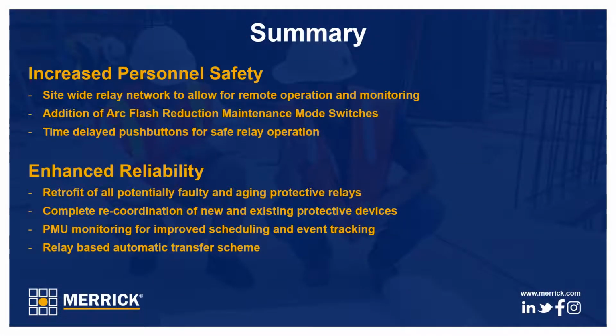In summary, the project was completed on time and under budget with the help of using a stage gate front-end loading engineering method while implementing lessons learned from past relay upgrade projects. The project increased personnel safety through the creation of an arc flash reduction program, integrated a plant-wide relay network to allow remote operation and monitoring, and added other features like time delayed pushbuttons for safe relay operation. Reliability was enhanced by replacing the aging assets, creating a system model to support the protection settings coordination, and the addition of the relay-based automatic transfer scheme.